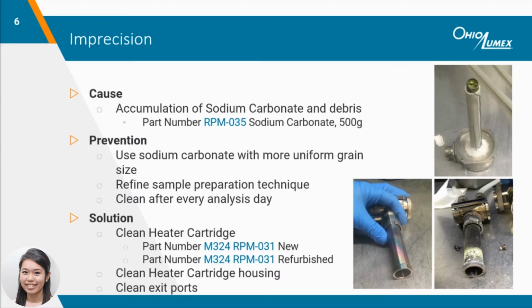When preparing a sample, make sure to compress the loose sodium carbonate in the ladle to prevent the soda from dispersing inside the attachment. Daily cleaning is a good practice, but it cannot reach some of the places in the attachment, resulting in buildup over time. When imprecision starts to occur, it's time to perform additional cleaning procedures, such as cleaning the heater cartridge and housing, as well as the exit ports. If you're in a time-sensitive situation, keeping an extra heater cartridge on hand is helpful to quickly swap out when you don't have the time to allow for the dirty heater cartridge to cool down, clean, and dry. I'll demonstrate in the next slide how to properly clean your heater cartridge. Other good indicators of buildup are when ladles come out of the attachment discolored or when it's difficult to insert a ladle without much force.